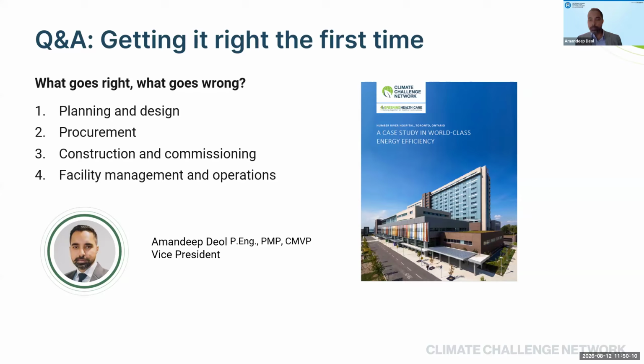So either there's a gap in the specifications to start with from the owner's side to ensure that performance commissioning is one of the tasks in the whole process, or it's completely missed in that scope. Even the commissioning agent is still working on functional commissioning rather than performance commissioning. So it's not a rushed activity to optimize these systems. This becomes a process change at the start of the design, even prior to setting up the performance requirements for the hospital. The key thing is ensuring that the specification calls for those performance specifications in those systems. That would help to bridge the gap that you typically see in the system.